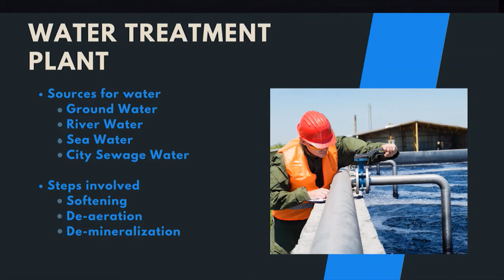Primarily, we try to soften the water, because hard water will form scaling inside the refinery equipment. It has to be softened and deaerated - all the dissolved gases, either oxygen or carbon dioxide, need to be removed from the water. Then finally you have to remove all the minerals. This is essential to produce steam in a boiler - we need demineralized water. Removing minerals using ion exchange is one step in the water treatment plant, and this is an essential step in refinery utilities.